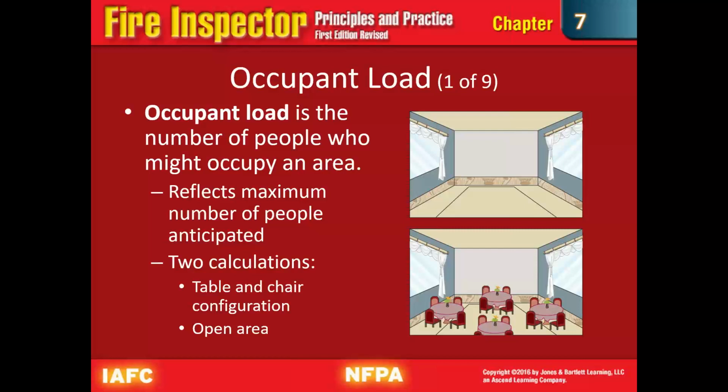But then think of that same kind of setup and then think of a church house. Then you're basing it on how many inches, and typically it's 18 inches per person. So you have to measure out the pew and see how many times 18 can go into whatever measurement I obtain, and that's how many people are going to be able to sit at this pew. And you calculate for each pew in the sanctuary area, and that's going to give you your occupancy.